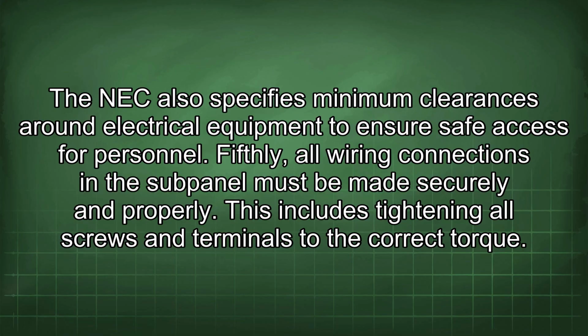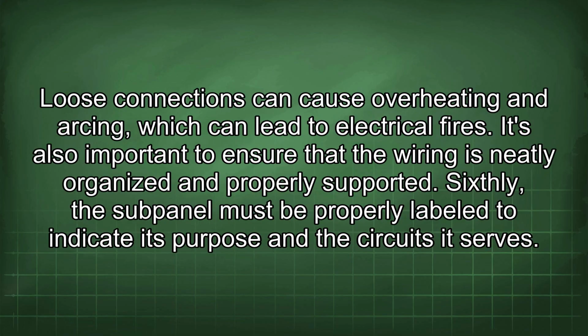Fifthly, all wiring connections in the subpanel must be made securely and properly. This includes tightening all screws and terminals to the correct torque. Loose connections can cause overheating and arcing, which can lead to electrical fires. It's also important to ensure that the wiring is neatly organized and properly supported.